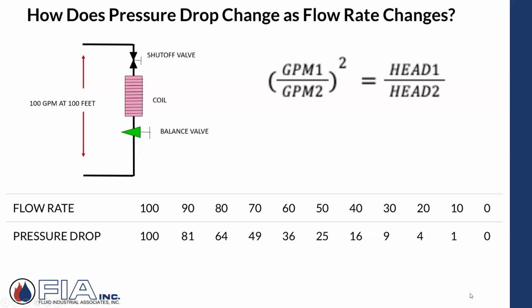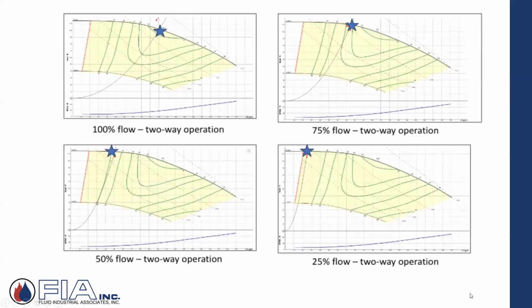So if I have this modulating valve, I have modulating pressure drops because I have reduction or increase in flow. But that's changing all the time with these two-way valves. And that applies to that variable speed that we're going to get into as those system conditions are changing. So in reality, you have a system curve. Well, you have multiple system curves, actually. And they change depending upon where the flow is. Is it 100% design conditions? Okay, here it is. Is it 25% closed, only 75% flow? Here's my new system curve within that constant speed application.